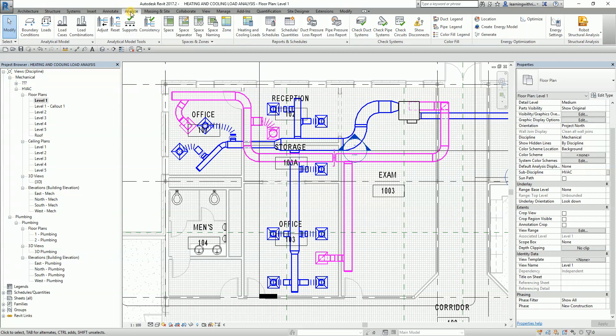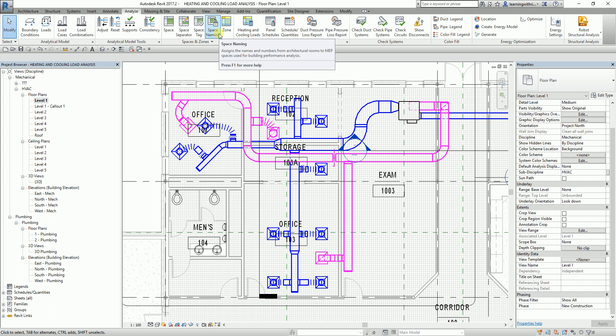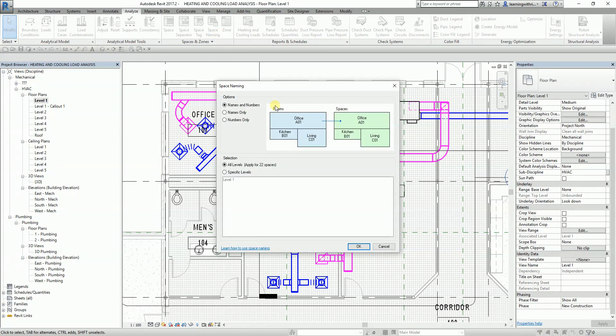You go to Analyze, and you can see the Space Naming tool there. Even if you are not on subscription, you should be able to see this Space Naming tool. It assigns the names and numbers from architectural rooms to MEP spaces used for building performance analysis. So instead of changing spaces manually, you just select Space Naming. The options here are Names and Numbers — the spaces will follow the name of your room, which is very useful.